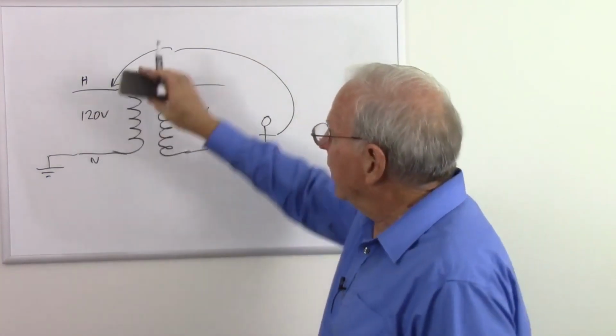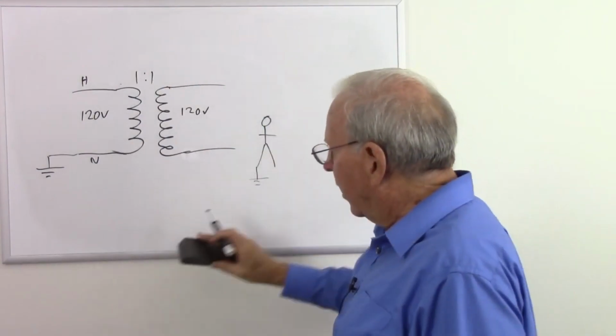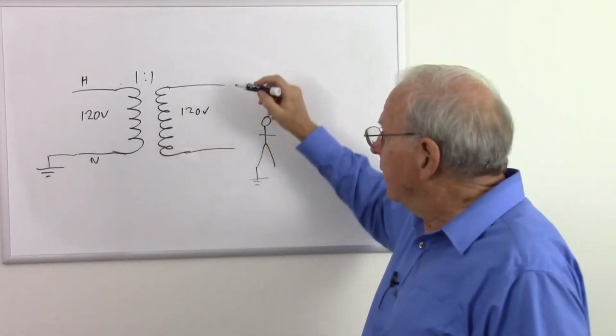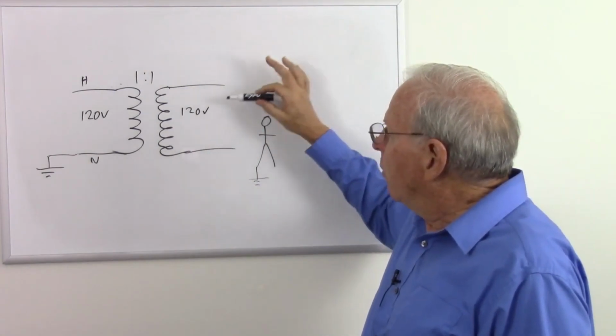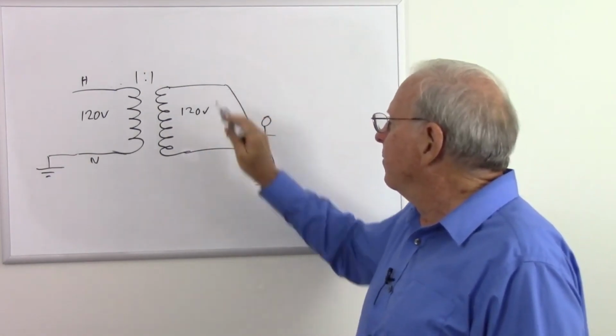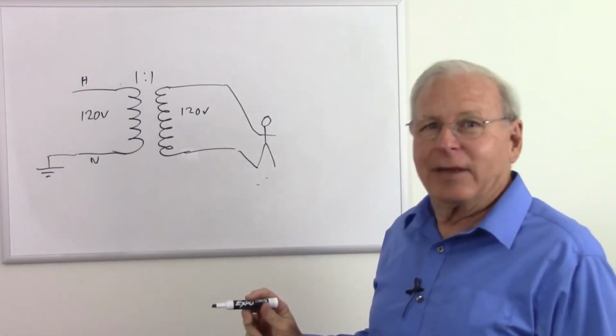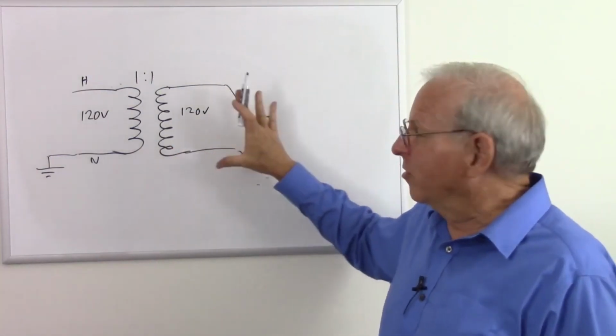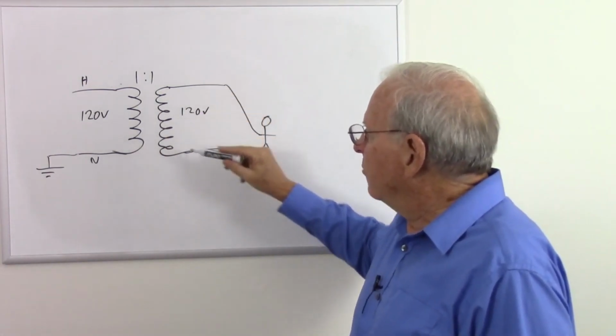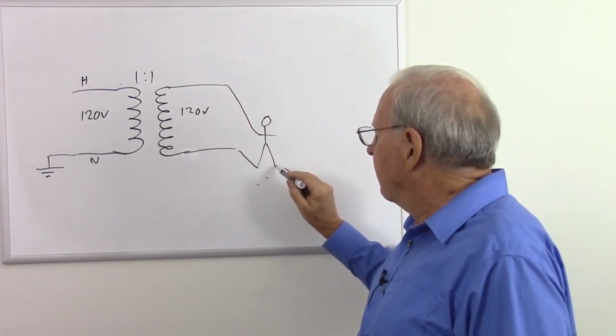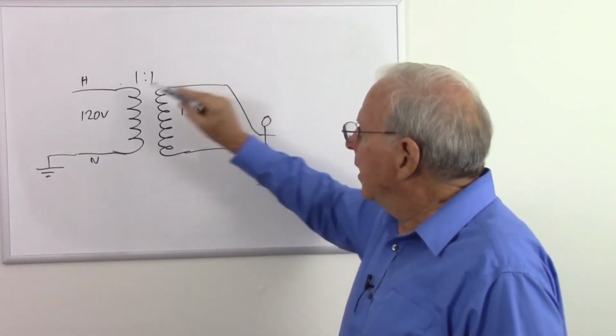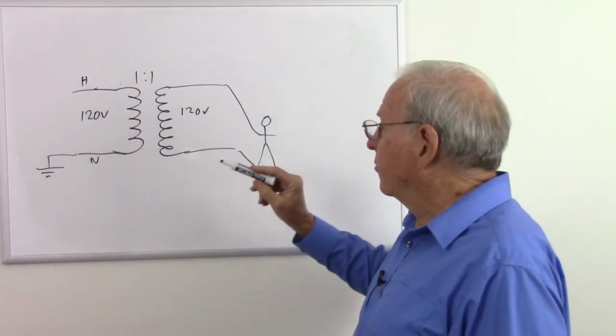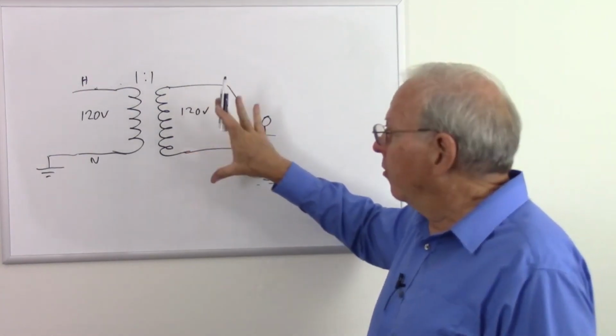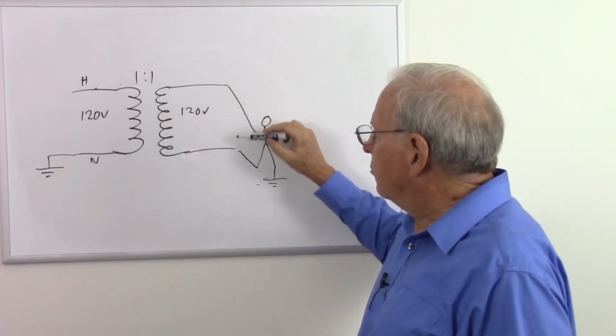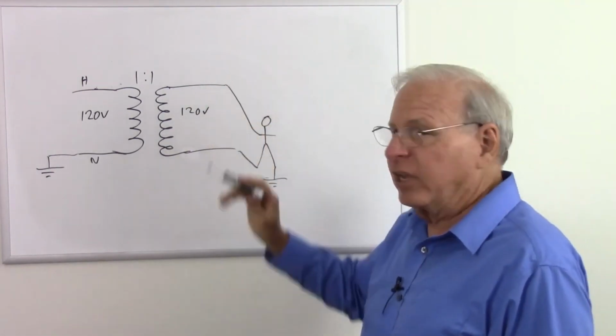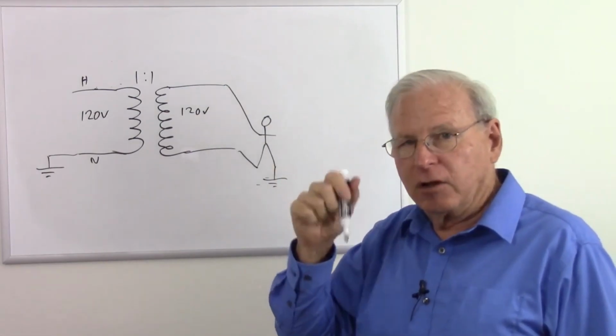But on the secondary, I have to actually touch both wires, since neither of them goes to ground — my voltage is between that wire and that wire. To get a shock, I'd have to put a hand on one and a foot on the other, which is very unlikely, especially with double insulation and so on. So with an isolation transformer, if I'm connected to ground, it's dangerous to touch one wire on the hot side, but on the delivery side I'd have to touch both wires to get a shock. So it's a measure of safety. I'll go into more detail on that in another linked video.